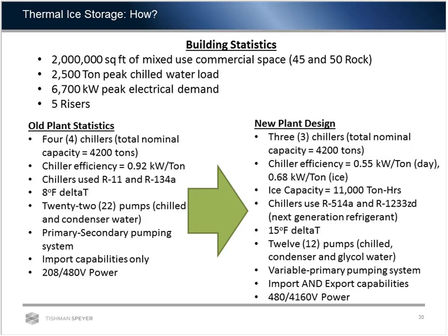We designed a plant that fit in almost the same footprint as the last one, but had a gigantic amount of firepower in the form of chillers, pumping, and thermal storage. We had the luxury of voltage changes to the machines, as well as increasing delta T of the machines themselves during design, and reducing the amount of pumping through primary pumping strategies. We'll get to some of the successes in the pictures I'll go through in a second.